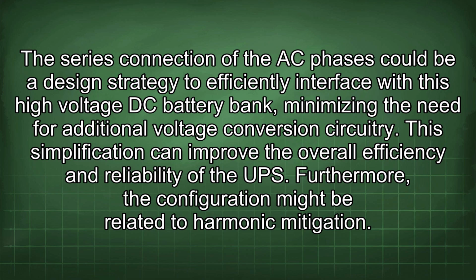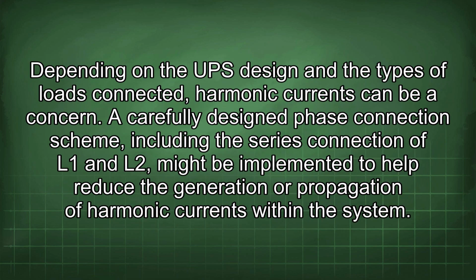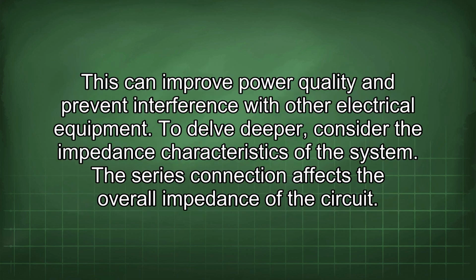Furthermore, the configuration might be related to harmonic mitigation. Depending on the UPS design and the types of loads connected, harmonic currents can be a concern. A carefully designed phase connection scheme, including the series connection of L1 and L2, might be implemented to help reduce the generation or propagation of harmonic currents within the system. This can improve power quality and prevent interference with other electrical equipment.